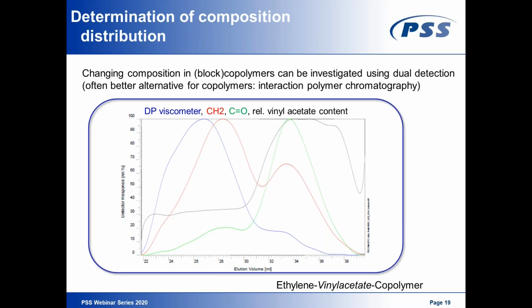And this kind of dual detection can be done very easily. You see here that we just need two different concentration detector signals. This would, for example, also work for the polystyrene PMMA copolymer I've shown you in the beginning. So every time you have two comonomers reacting differently to concentration detectors, you will be able to have at least an idea if you have an identical composition over all molar masses or if the composition changes with your molar mass. This can be done in both ways, very simple like we've done here, but of course you can also quantify that and use two different calibration curves and can then measure the molar mass distribution of your block copolymers.